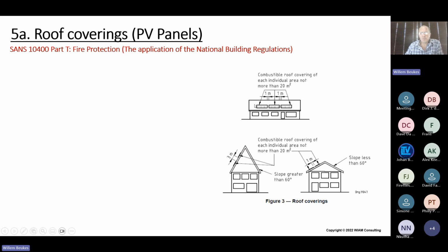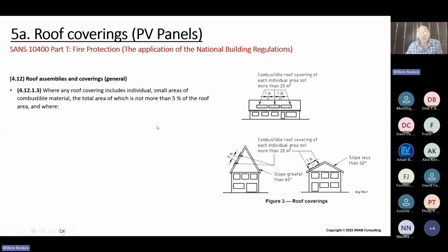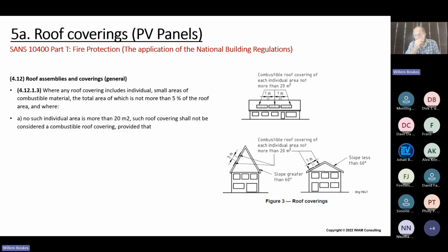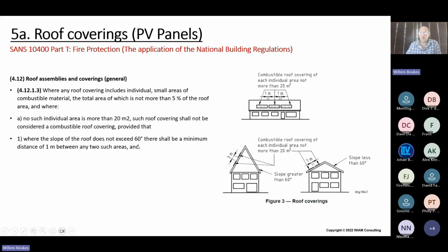So with this in the backdrop, when we look at PV panels and combustibility of roof coverings in South Africa, the regulation states that when you have a combustible area or material that you place on a roof, for example, that's more than 5% of the roof area, you have to have a rational design from a professional engineer to ensure that this combustibility component of the roof is being met. Then it also gives a section where it states that no area of this combustibility component needs to be more than 20 square meters of area, and depending on the slope of your roof, whether it's below 60 degrees or higher than 60 degrees, there needs to be at least a 1 meter spacing between these combustibility components that you put on the roof.